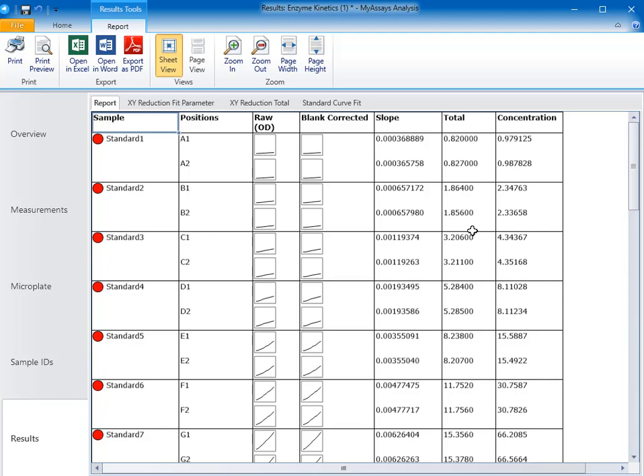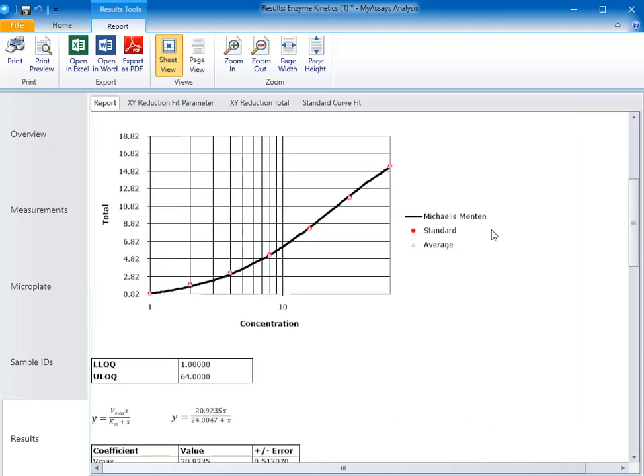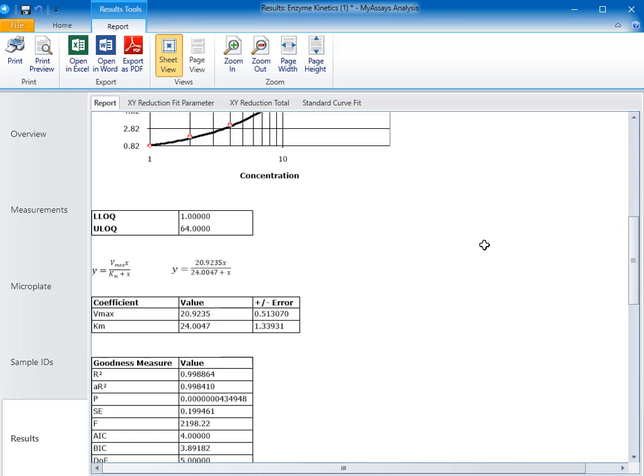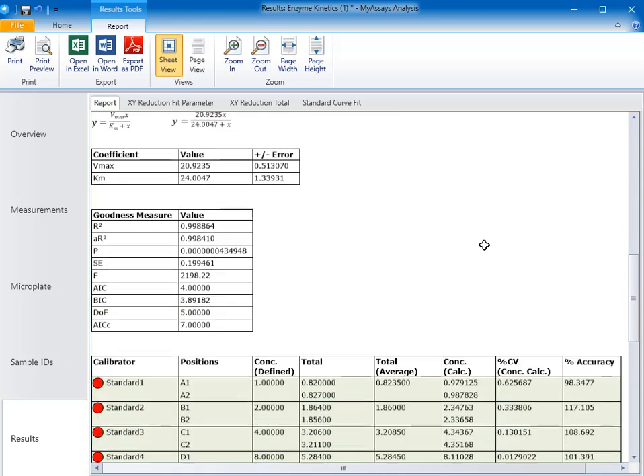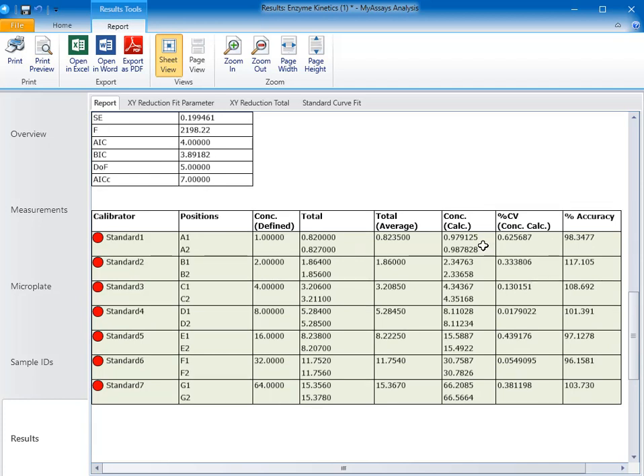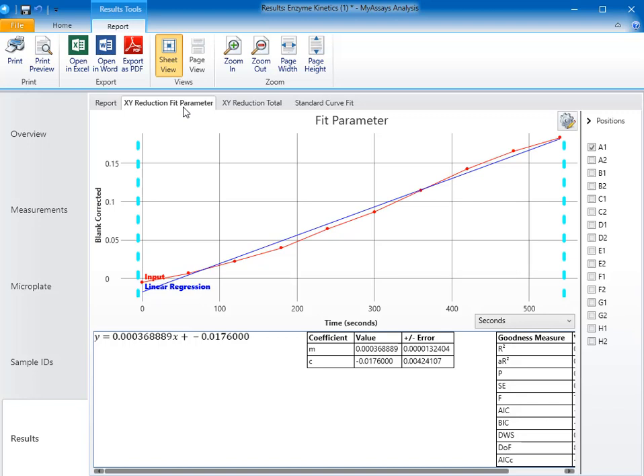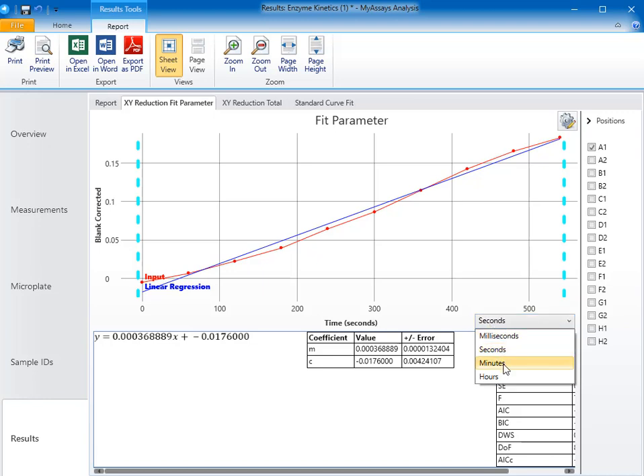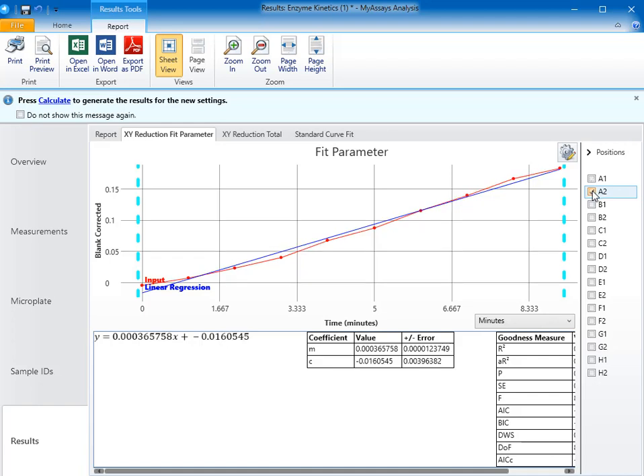Below the sample table, you'll see the standard curve fit, as well as the corresponding details, like limits of quantification, coefficients, and goodness measures. You'll also see the curve data table that shows the calibrators and their associated information. The standards that have acceptable percent CV and accuracy results, as defined using the quantification limits in the standard curve fit transform, will be highlighted in green, and those that do not will be highlighted in red. On the XY reduction fit parameter tab, you can see the input is the blank corrected data, and the linear regression fit line for each position, as well as the fit details below. You'll notice the X axis is showing the time in seconds, but if I'd like to display this axis in minutes, I can just make that selection from the drop-down box. I can view the different positions by selecting their checkbox on the right.